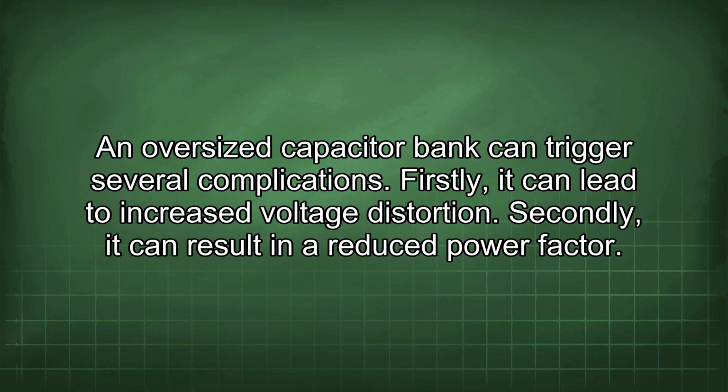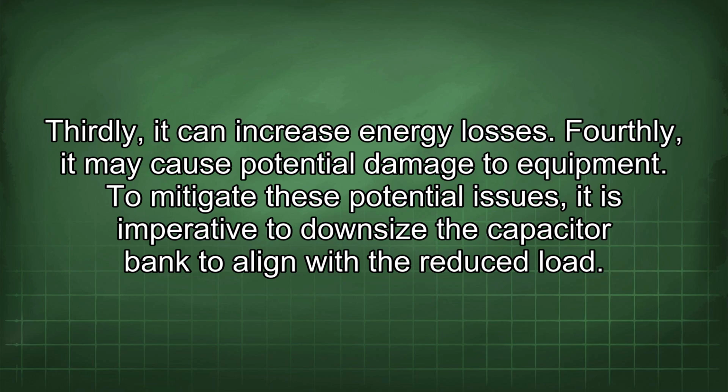An oversized capacitor bank can trigger several complications. Firstly, it can lead to increased voltage distortion. Secondly, it can result in a reduced power factor. Thirdly, it can increase energy losses. Fourthly, it may cause potential damage to equipment.